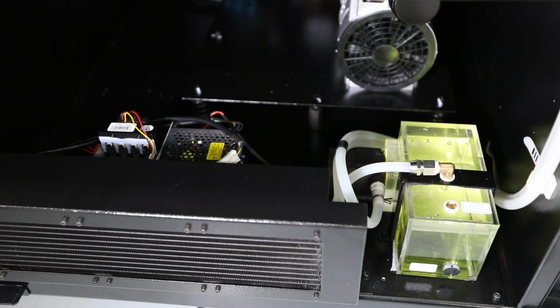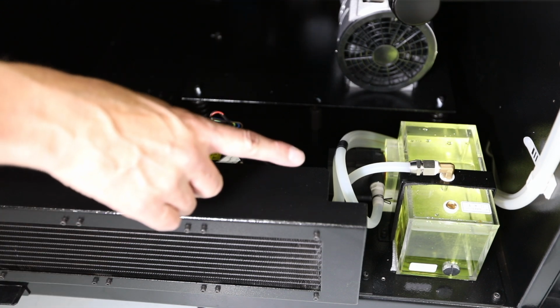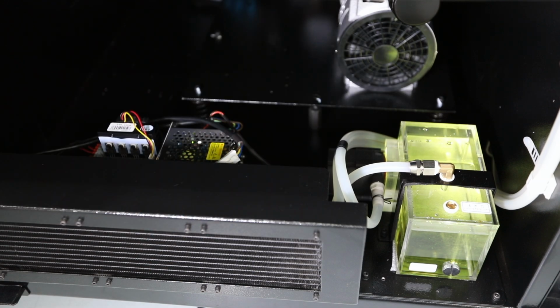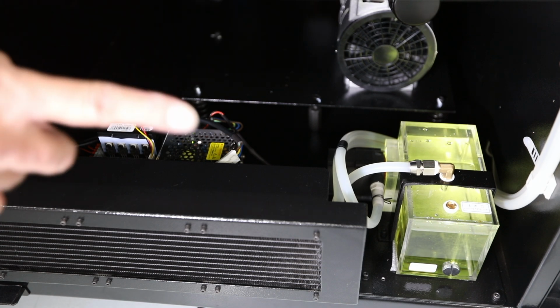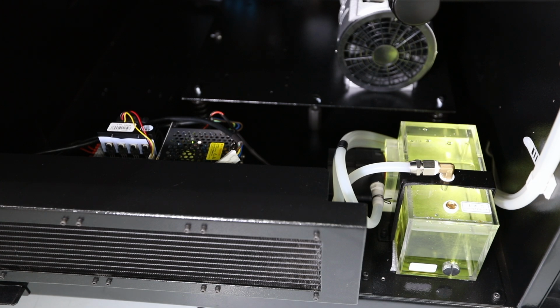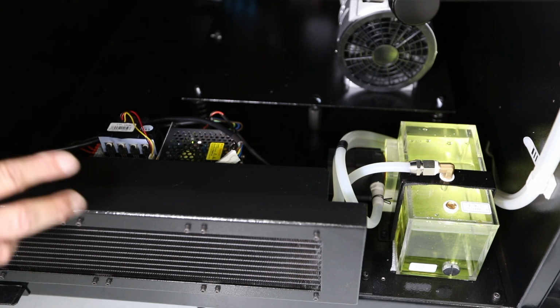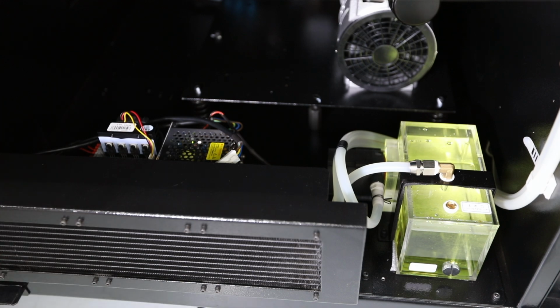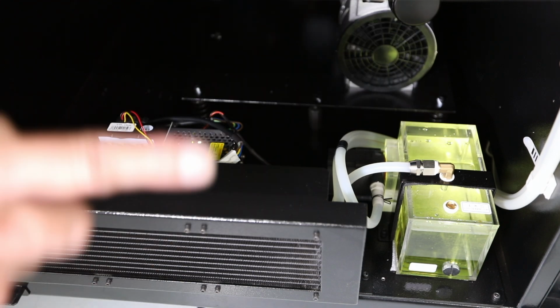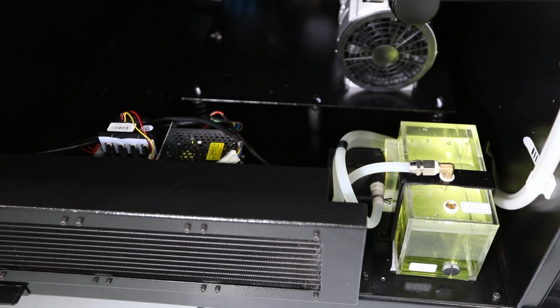So the CRON laser head systems are accurately cooled using a liquid cooling system. On the right here you'll see our coolant tank. This is using glycol, which you can buy from any car parts store. We don't sell the consumables. The liquid is flowing up to the imaging head and then back down through a radiator here, where the fans are blowing out the air through the radiator to complete the loop. So it's a closed loop liquid cooling system. We have a top-up tank, and basically in the field that will just require checking and topping up once per year.